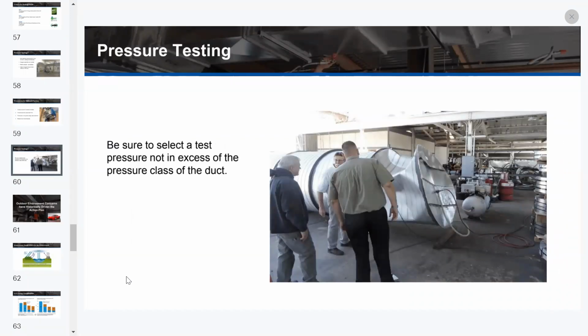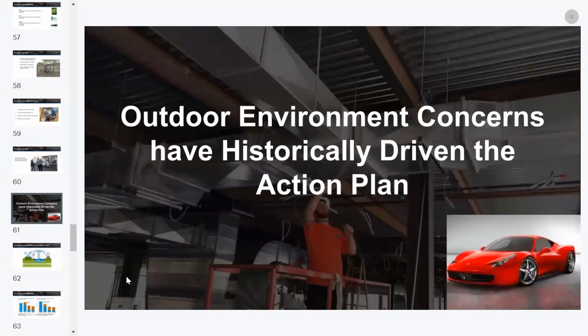When you're talking about test pressure, and this next slide shows that perfectly, one of the key things, as an engineer myself, is that you always want to test 2 to 3 times for a safety factor and all that. But when it comes to ductwork, you need to test to the pressure the ductwork is rated to run at or is actually running at. Because if you apply excess pressure, you can collapse the duct, you can explode the duct, and with that 2 to 3 times safety factor, you'll permanently damage that duct system. And if you're the guy doing the testing, then you're also going to be the one replacing that duct system.